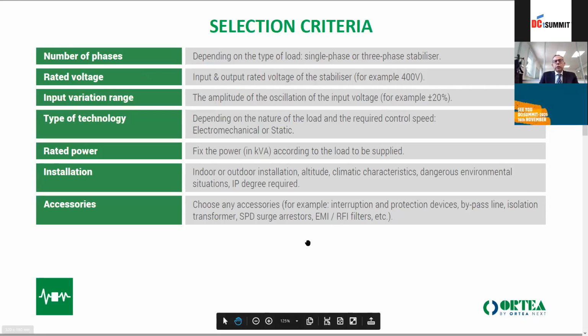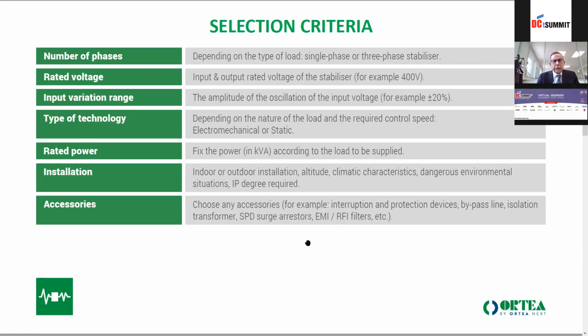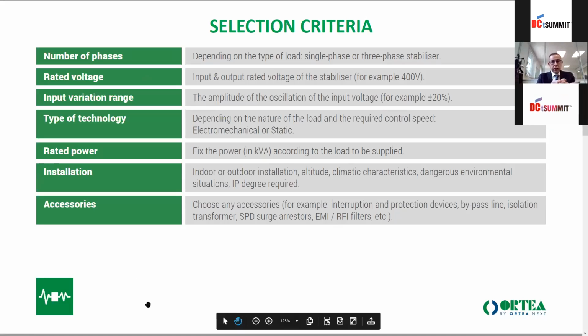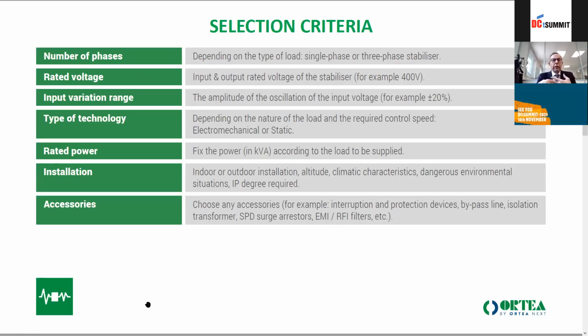So how to proceed with the selection of stabilizers? Very easy. You need to know the number of phases you have, single phase or three phase, the nominal voltage of your line, and the variation of your voltage on the input side, so how much it is plus or minus. This is very important, because sometimes people do not think that having a very high variation, especially in minus, introduces a very high current and has a big influence on the construction of the unit.